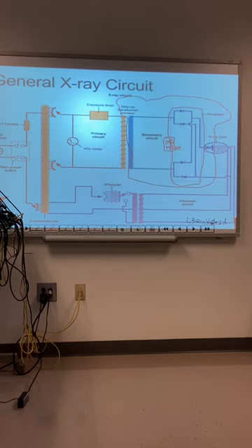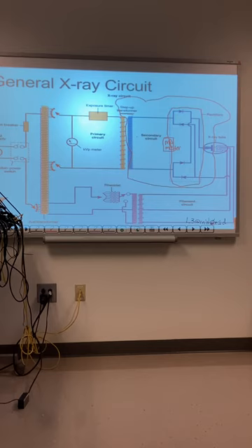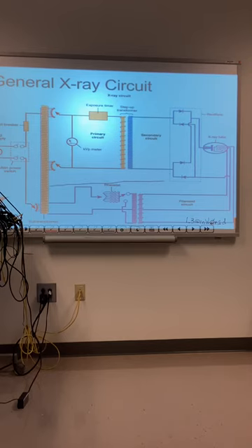In your secondary circuit, all you need to talk about is the step-up transformer, the mA meter, and the rectifier. So secondary is easy. Just hope you don't get the primary, because there's more going on in the primary, to me. Now we're going to erase that, and we're going to go to your filament circuit. Secondary is not extensive, but they're recording it.